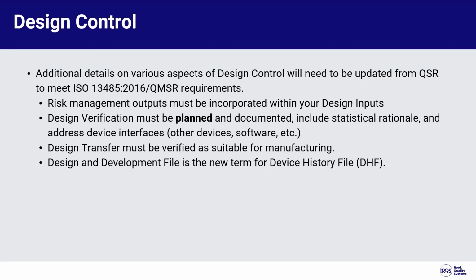Another thing is for the design verification, you have to make sure you're including statistical rationale and addressing device interfaces. So if your device is interfacing with a software system or another device or a non-device, you need to make sure that design verification addresses those interfaces explicitly.